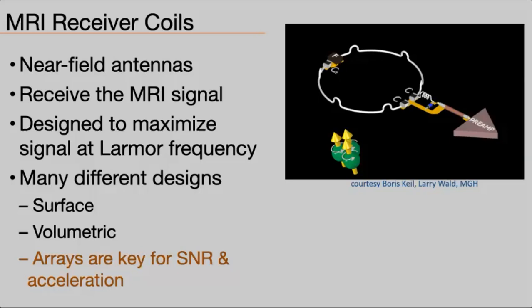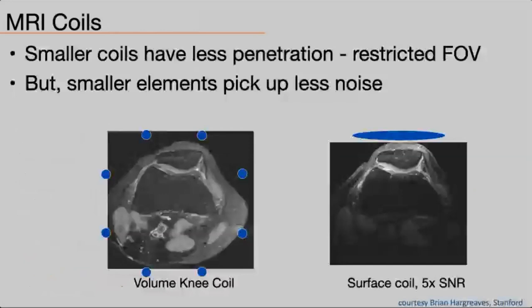Okay, while smaller coils have limited penetration in comparison to volume coils, they also pick up much less noise from the sample. And this is kind of what we talked about in the past. So you can see that the surface coil provides much higher SNR close to the coil than a volume knee coil, but it has a limited field of view.